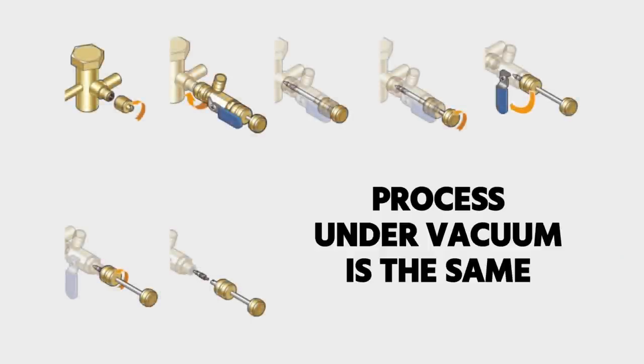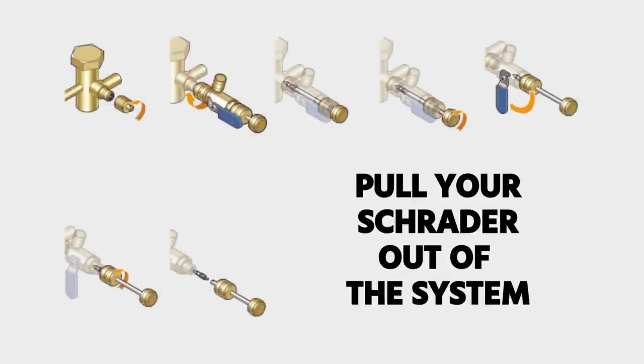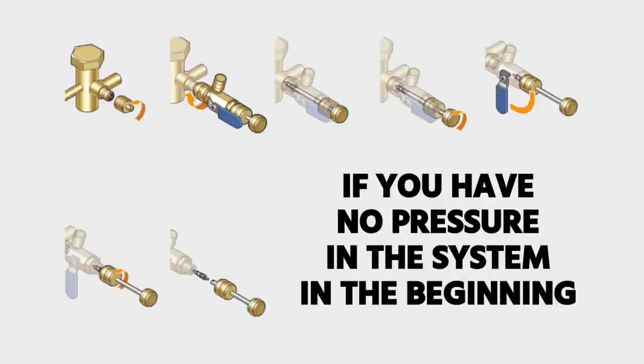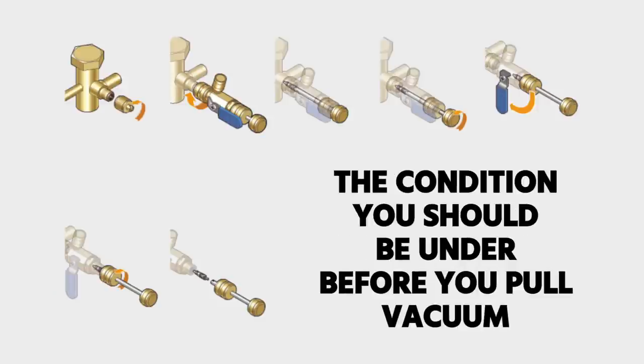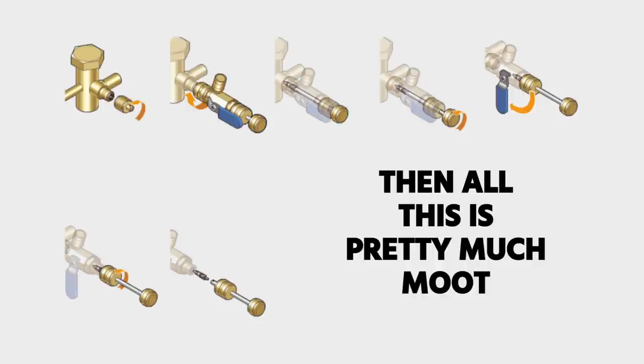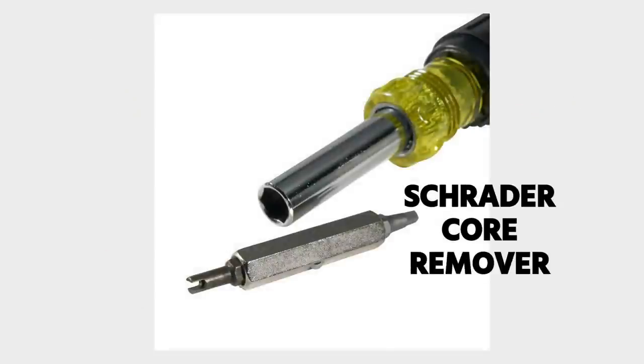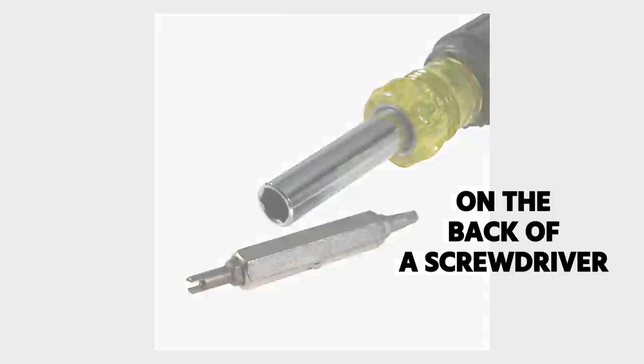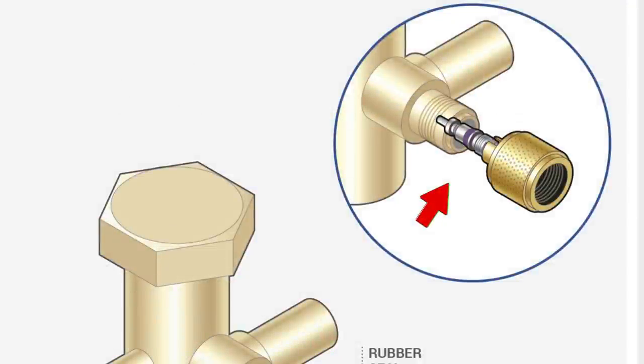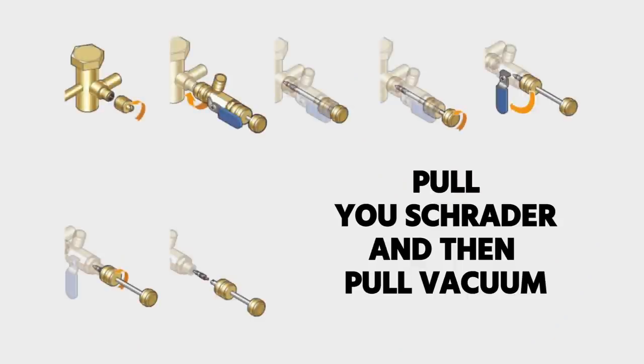The process under vacuum is the same. You're going to pull your Schrader out of the system. If you have no pressure in the system to begin with, which is the condition you should be under before you pull the vacuum anyway, then all this is pretty much moot. You could really just use a Schrader core remover on the back of your screwdriver or on the back of your cap here, like shown. Some of these caps have a Schrader core remover right on the cap itself, and you're going to pull that Schrader out, and then you're going to pull your vacuum.